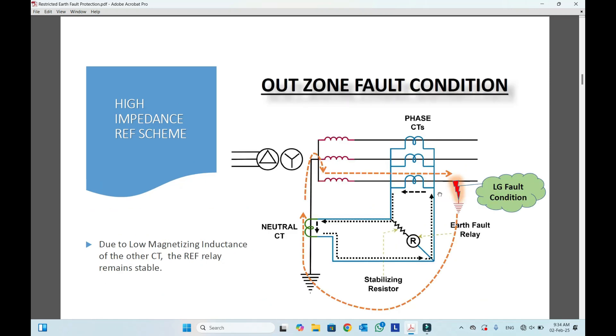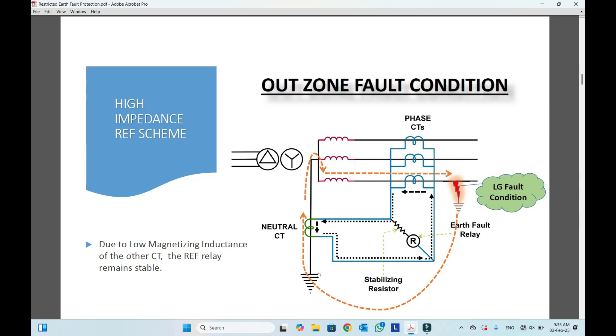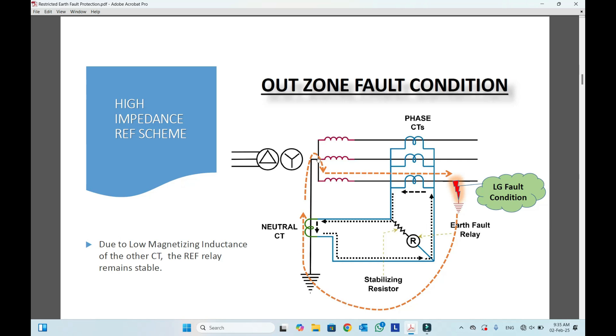There is an example for REF high impedance scheme out-of-zone fault condition. When there is a fault outside of this zone, this relay will be stable. For a line-to-ground fault, the current will flow to earth. The neutral point of the transformer is also connected to ground, so the current will flow to ground, take the ground path, return back to the neutral, and go to the neutral part of the transformer. This current will flow through the neutral CT as well. As you know, the current entering P1 or P2 of the primary will leave from S2 or S1 of the secondary side. Similarly, here the current is passing through the phase CT, entering at that terminal, so the secondary current will leave the same terminal.